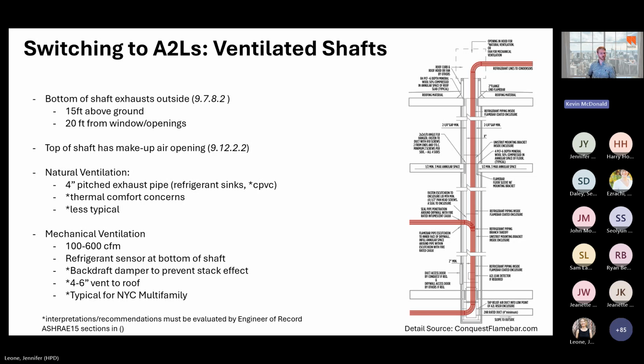So generally, you are venting from the bottom of that shaft, and that needs to discharge outside of the building, somewhere 15 feet above the ground or 20 feet away from window openings, and also not into an open air ventilation shaft because it can pool at the bottom and be a fire risk there. At the top of these fire-rated shafts, there needs to be a makeup air opening, so you could draw air in from the top, and then the refrigerant, if it leaks, could fall out the bottom and then push out that exhaust pipe at the bottom.